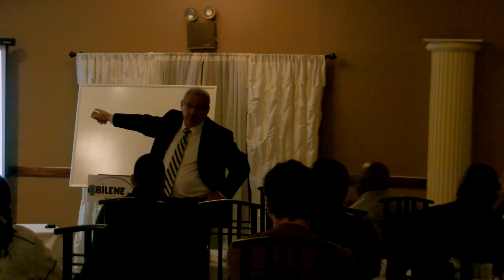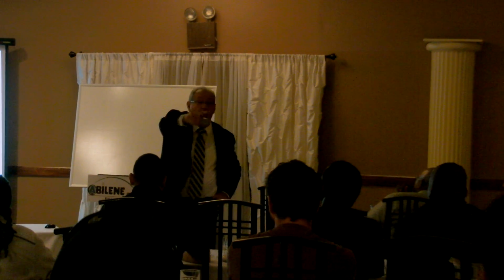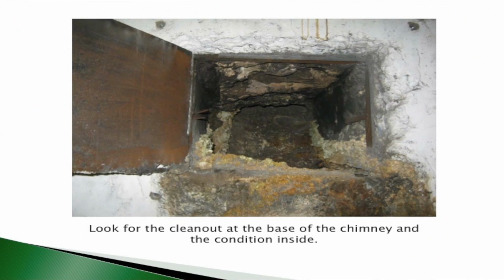Thank you, Vin. Now, what is that? I'm sorry, what is it? Clean out. It's a clean out, where? I'm sorry? Base of the chimney. Base of the chimney. So number one, you have to make sure that you have a clean out at the base of the chimney. Number two, you have to look inside to see the condition.